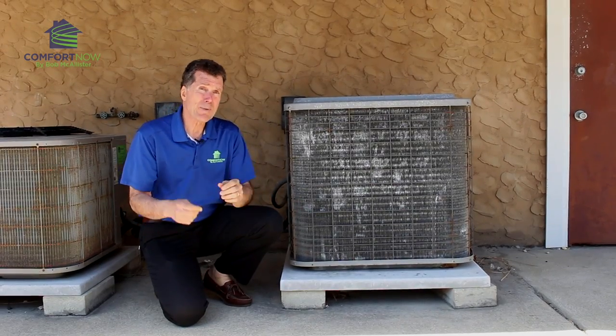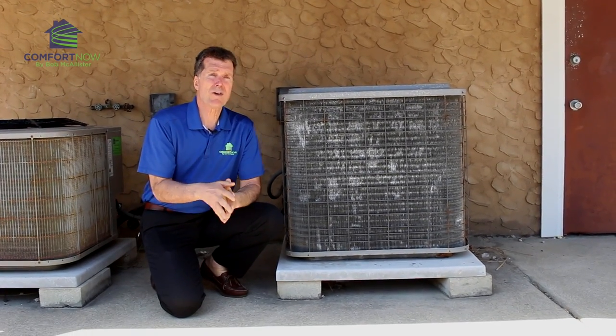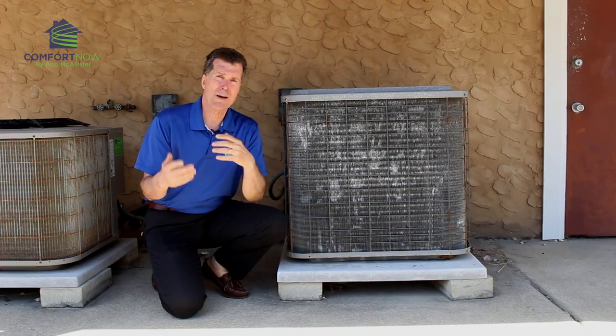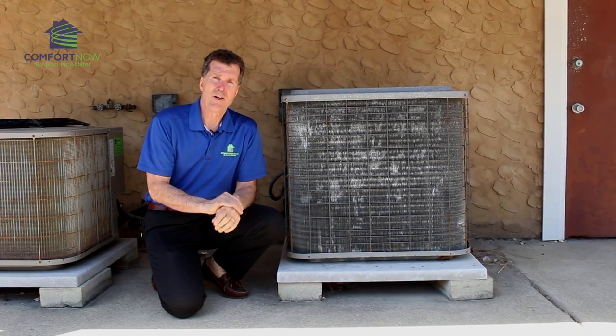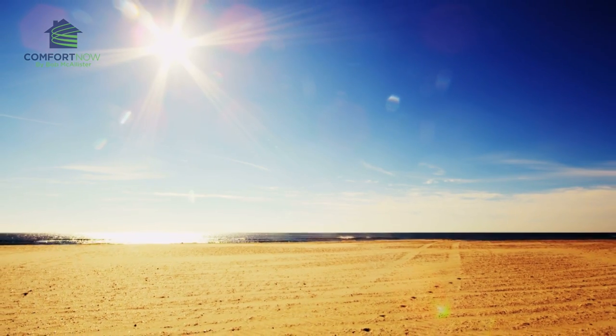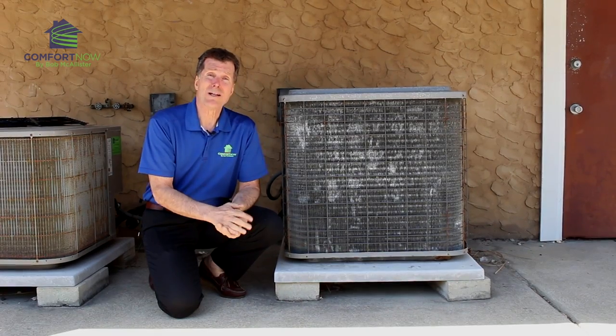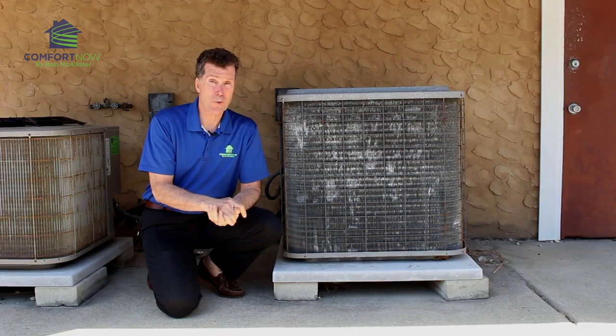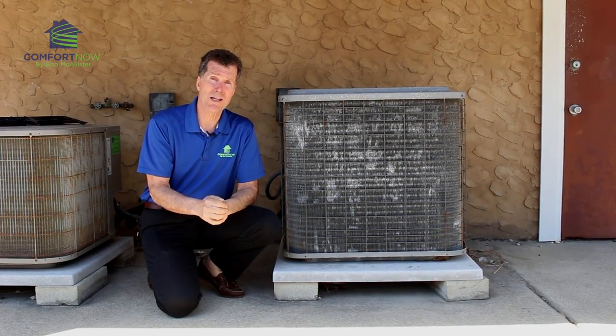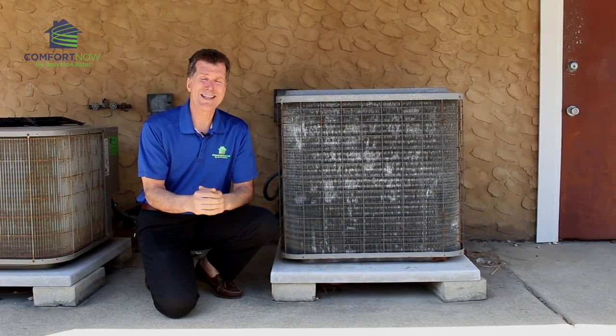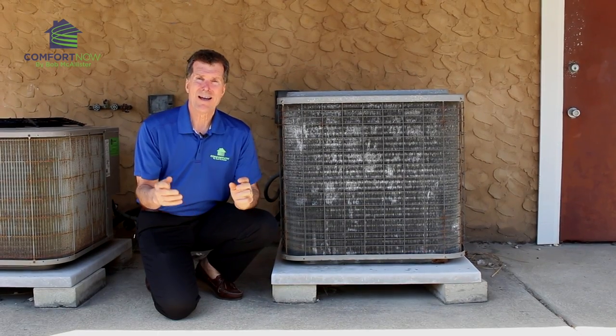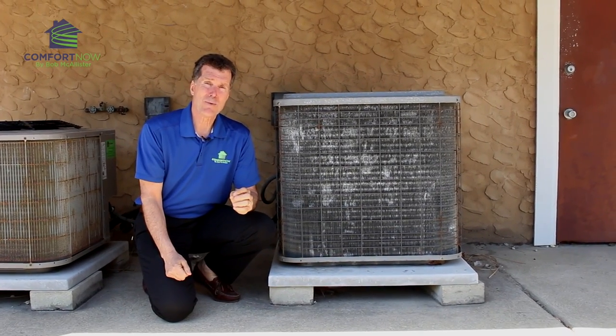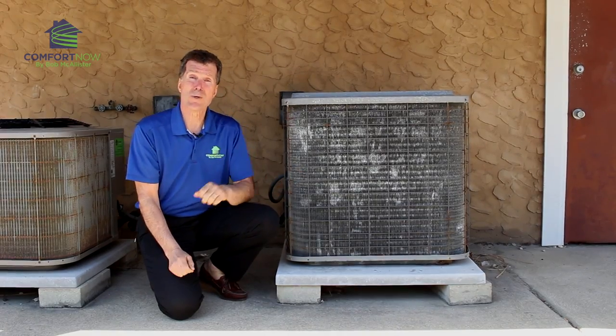What happens here at the shore is if we have a couple of mild summers, we forget about it because we don't need the capacity. Then all of a sudden we get a hot spell, it can be 100 degrees on the beach, and the unit isn't working, so these people will roast. That's when the calls really start coming in, because it's such a common complaint: 'my air conditioning isn't working properly, it's not cooling enough.' Probably 90% of the time we get that complaint, this corrosion issue is the reason why.